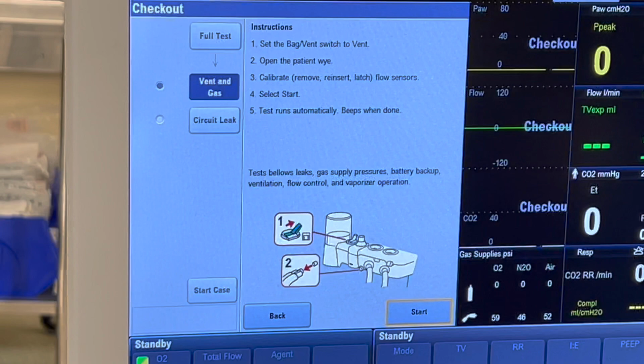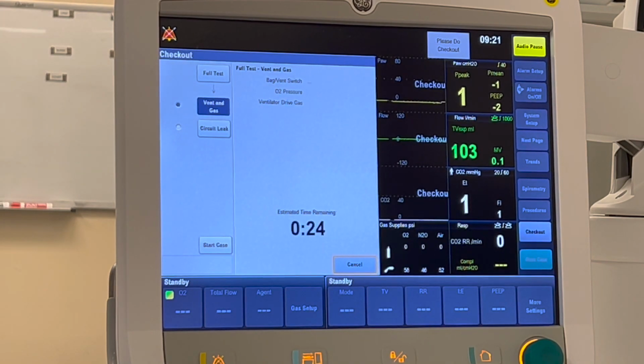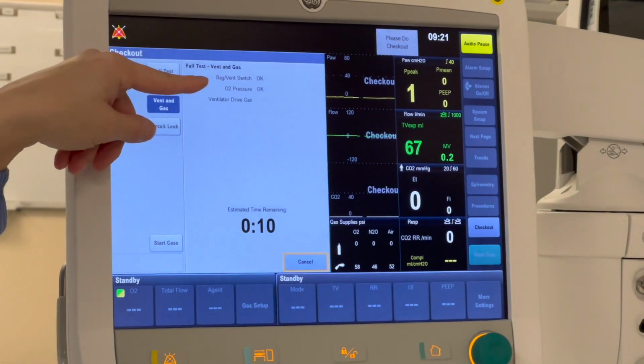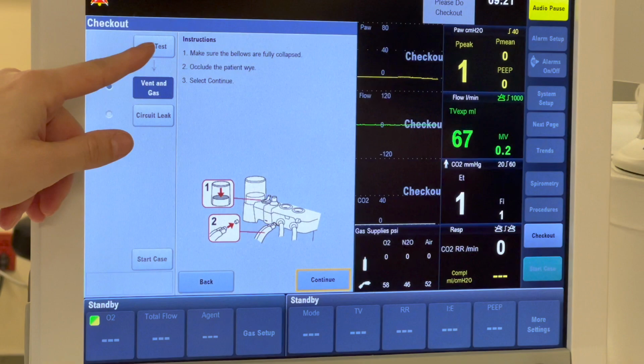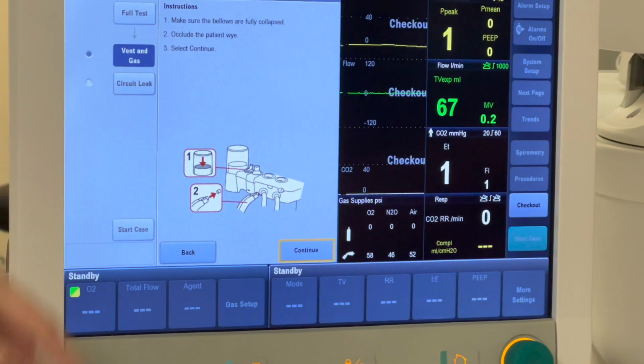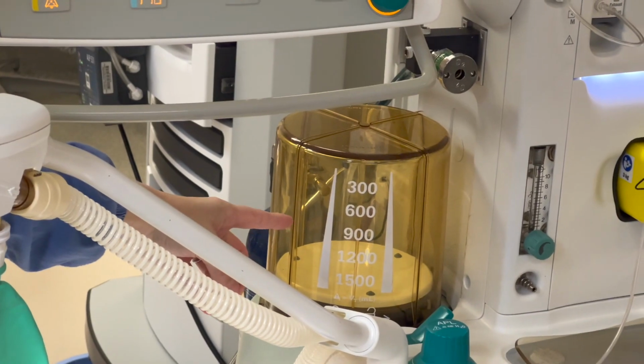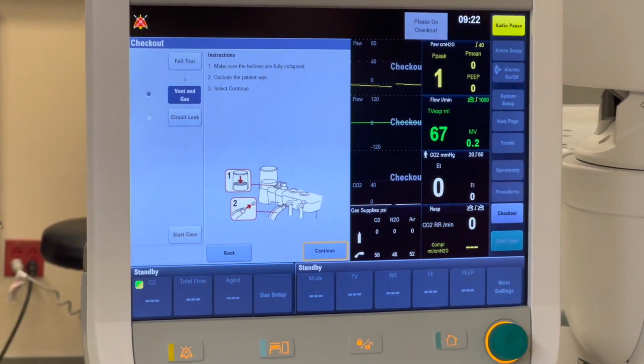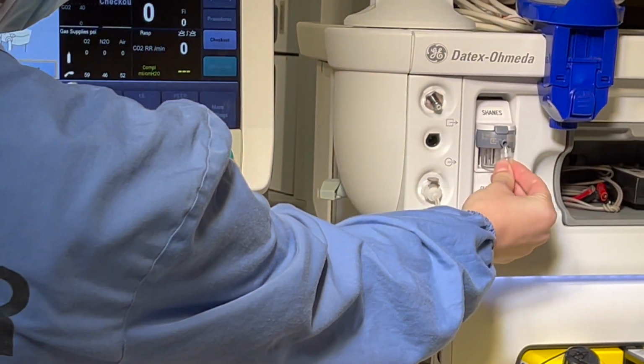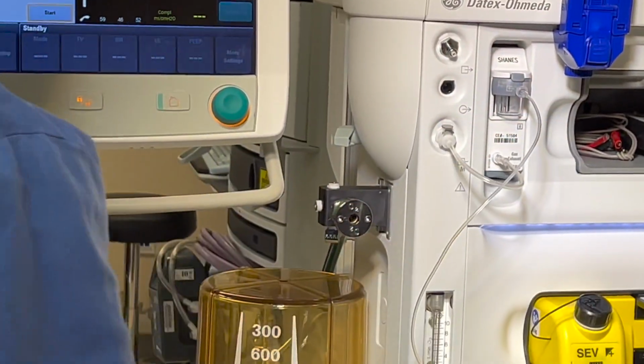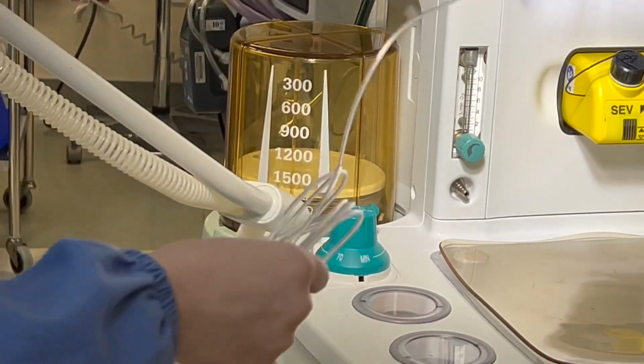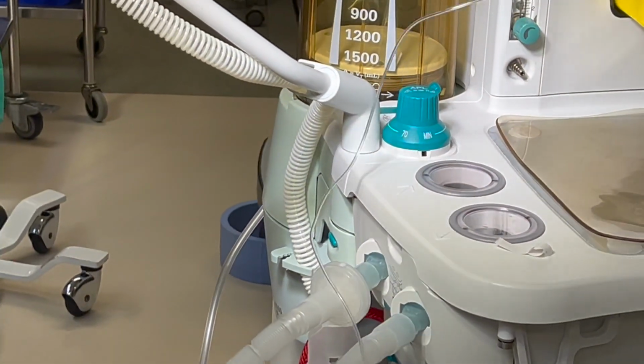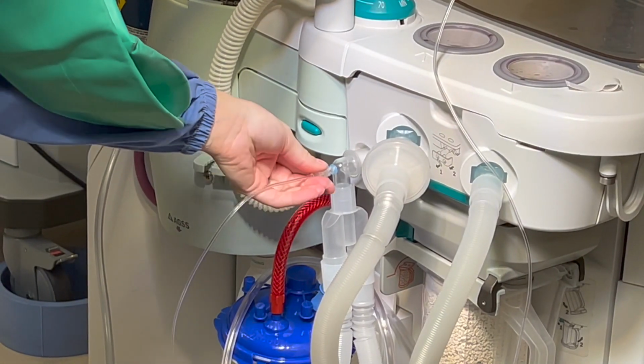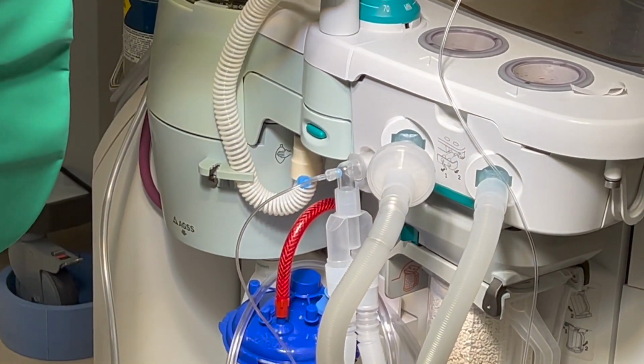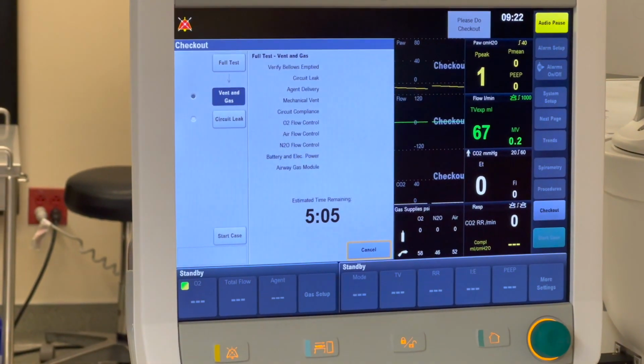At this point, you should go ahead and be able to hit the start button, which will initiate the first self-check, and this takes less than 30 seconds. If everything looks good, you'll move on to this step, which is to ensure that the bellows are fully collapsed, which they are, and then to make sure that the patient Y is occluded. And at this point, you can go ahead and connect your end-tidal CO2 and then connect it to the part of the patient Y that we had opened before. Then go ahead and return and hit continue.